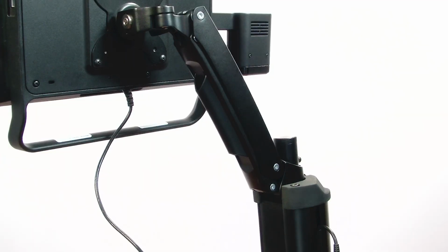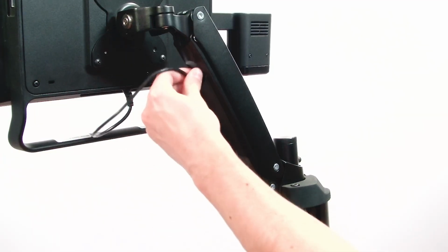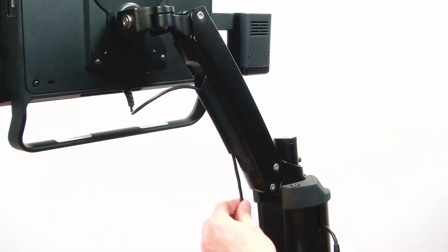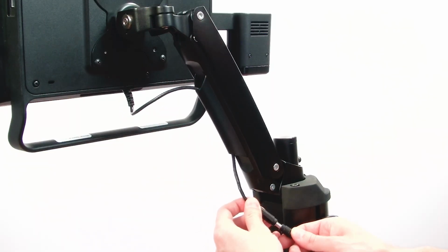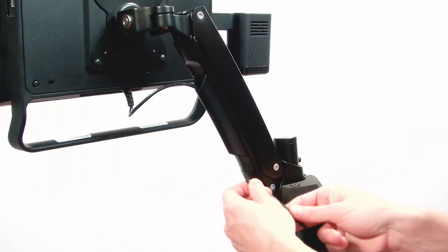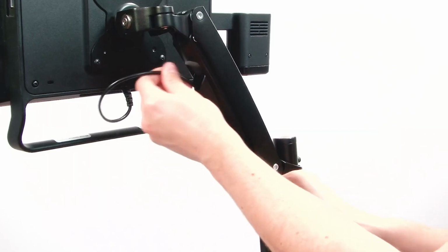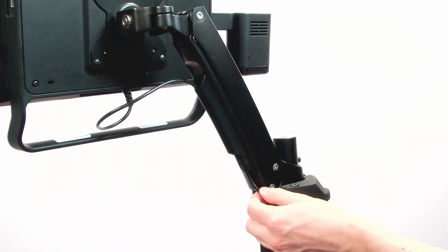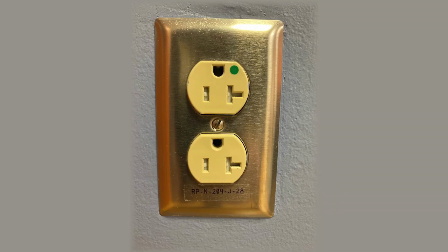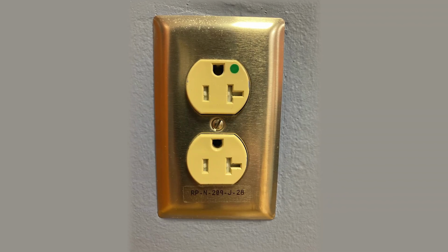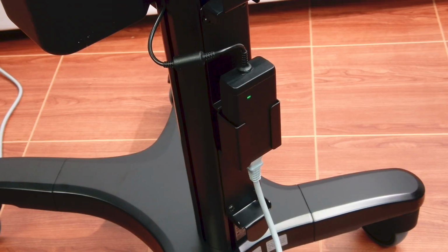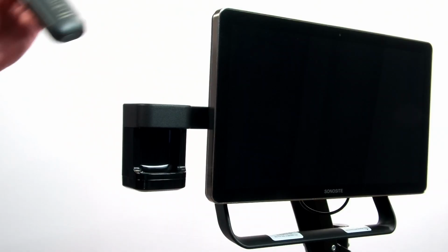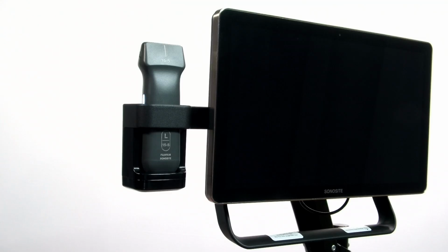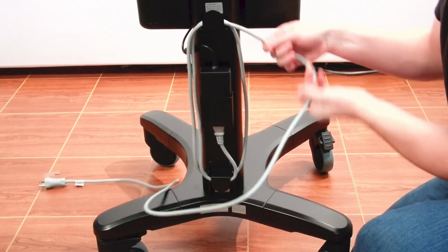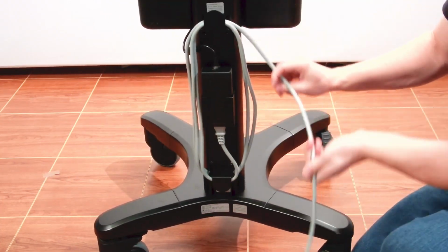Thread the system cable through the opening between the stand arm and the front cover of the stand arm until the cable connector appears at the bottom of the front cover. Connect the power brick cable to the system cable. Store the cable connector by pushing it towards the stand arm and sliding it up into the opening of the front cover. Plug the AC power cord into a hospital-grade AC mains outlet and ensure the power brick light is on. Place the transducer into the holder to charge it. Allow the system to charge for 4 hours before using it unplugged. When using the battery, keep the AC power cord wrapped around the cord wrap.